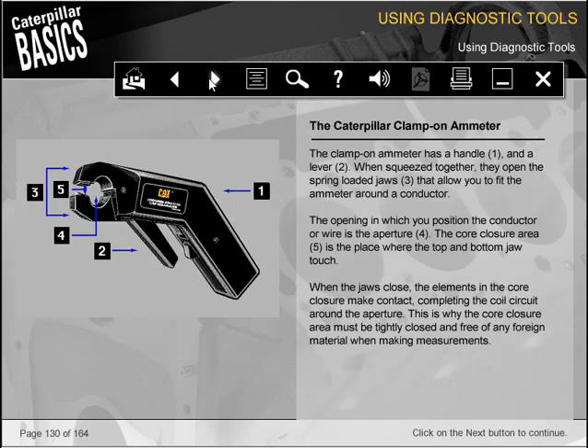The clamp-on ammeter has a handle, 1, and a lever, 2. When squeezed together, they open the spring-loaded jaws, 3, that allow you to fit the ammeter around a conductor. The opening in which you position the conductor or wire is the aperture, 4. The core closure area, 5, is the place where the top and bottom jaw touch. When the jaws close, the elements in the core closure make contact, completing the coil circuit around the aperture. This is why the core closure area must be tightly closed and free of any foreign material when making measurements.